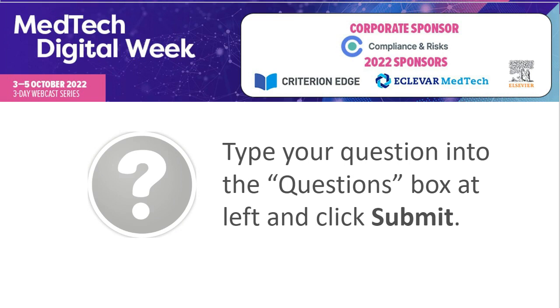So we're now getting into, and I just did a webinar on this, linking together clinical outcomes, claims, benefits, safety and performance objectives, all of this. There's that through line in the CER about linking your safety and performance objectives to the clinical outcomes that you expect, and then how that wraps up with clinical benefits. Benefits are for the technology, not your device in particular, and they are identified out of the state-of-the-art section review.